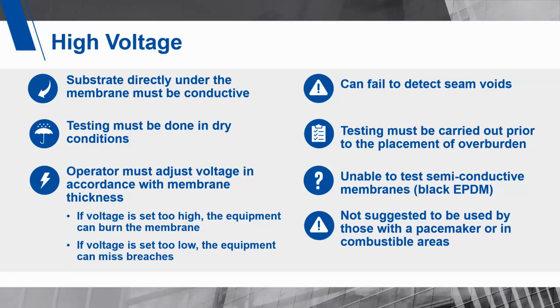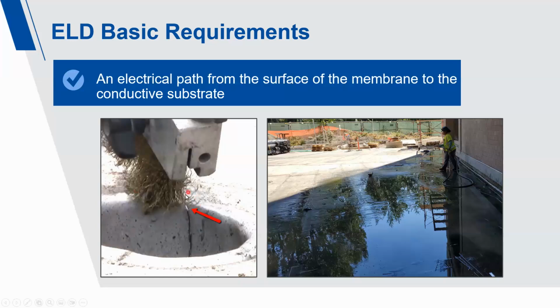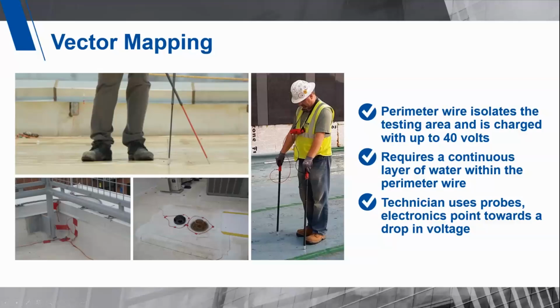This one is also not the best for seam void detection. That is because the spark only travels vertically through a direct vertical air gap. It does not bend or travel horizontally. So this requires a vertical air gap to spark. So seam void detection isn't the best with this method. As you all know, seams are overlapping, and this would only spark if there's a vertical air gap to the conductive substrate.